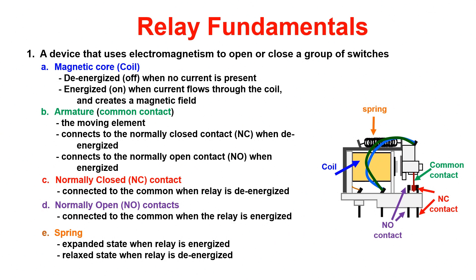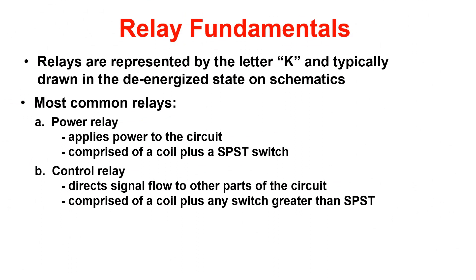There are multiple parts to a relay. Remember that relays are typically drawn in the de-energized state. The normally closed contacts are touching the common contacts. A magnetic core is utilized to develop a magnetic field, which allows the armature to be pulled into the normally open contacts, allowing current to flow from the common contact through the normally open contact. A spring returns the common contact to the de-energized state. Relays are represented on schematics using the letter K and are drawn in the de-energized state.